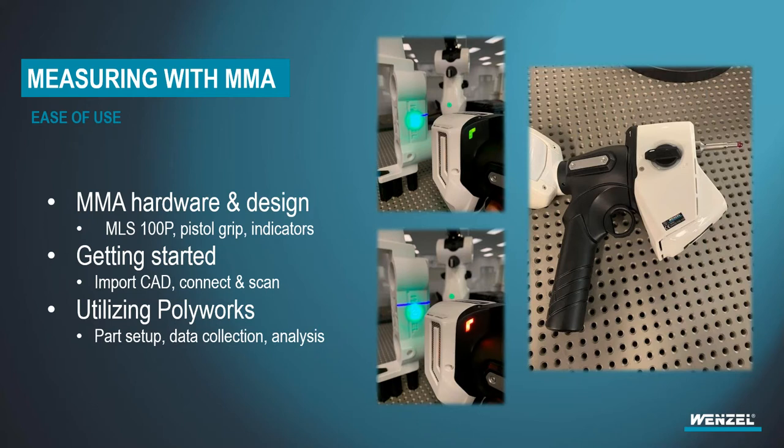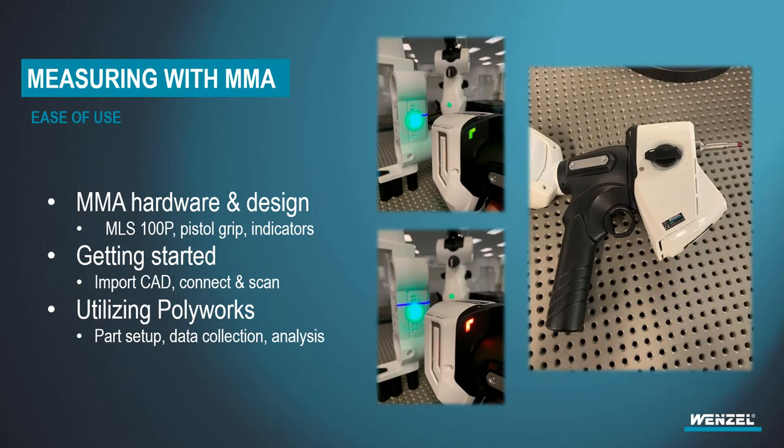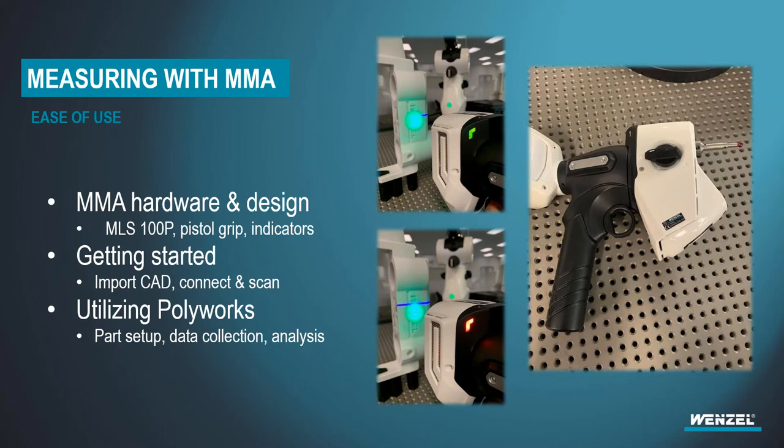So there is seven-axis to it. There's also the handheld device like you see here in front of you. It's a pistol grip with a push-pull trigger that starts and stops the scan, pauses the scan, starts to scan. There's also a thumb button on the top that accepts the scan when you're done. And it's a very easy interchangeable device. Whether you want to go with a tactile, straight tactile probe, or a combination of a laser tactile, or just the laser. The image on the far right, as you see, there's a little unlock switch on there, which allows the whole unit to drop out and replace it with something else.